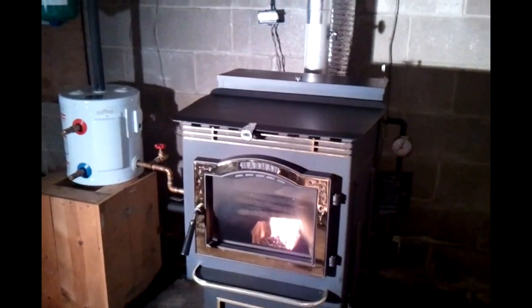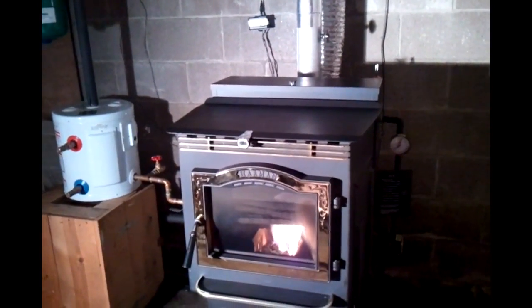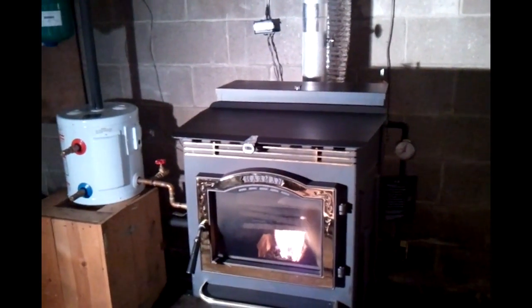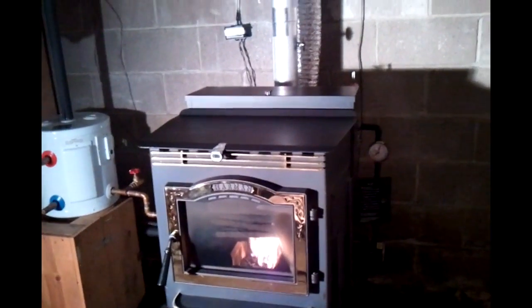Now I want to go over the operation of the system itself, and the safety devices included, and we'll go over the safety first. This can be run as an open or a closed system. Mine's a closed system, so I run with about 25 pounds of pressure. There's two 30 psi pressure relief valves. There's actually three. There's also one on the 6-gallon mixing tank.